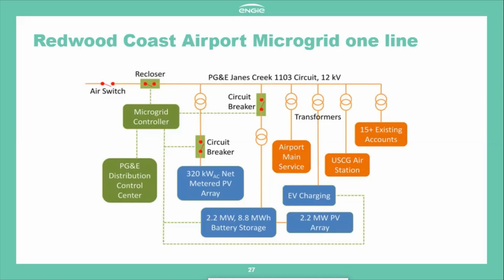So if it happens to be in winter where we're not getting a lot of solar, and it happens to be a morning outage where the battery storage isn't fully charged, we're going to have to curtail more of the load than we normally would. If it was in summer, in the afternoon, the batteries are fully charged, the solar's cranking, we wouldn't have to curtail any load. So really, as part of the design, we had to make some trade-offs, because they couldn't afford to put in a bigger battery storage system to make it 100% full utilization year round.